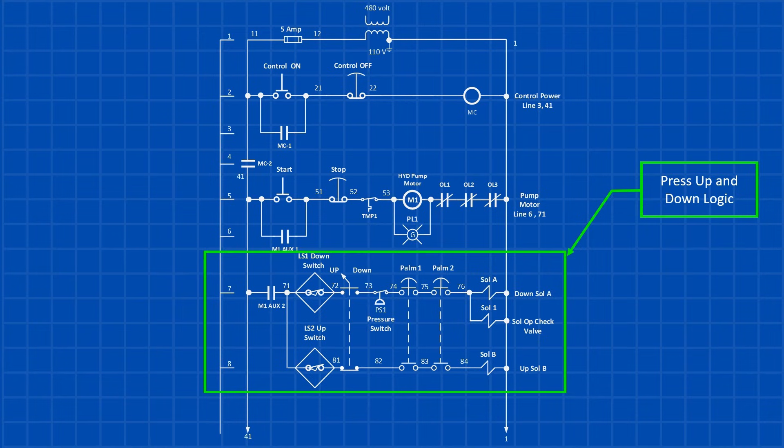For the press to move up, auxiliary contact 2 for the pump motor must be closed, ensuring the pump is running. The press up switch must also be inactive, as indicated by the normally closed press up proximity switch. Additionally, the up-down selector switch needs to be set to the up position.